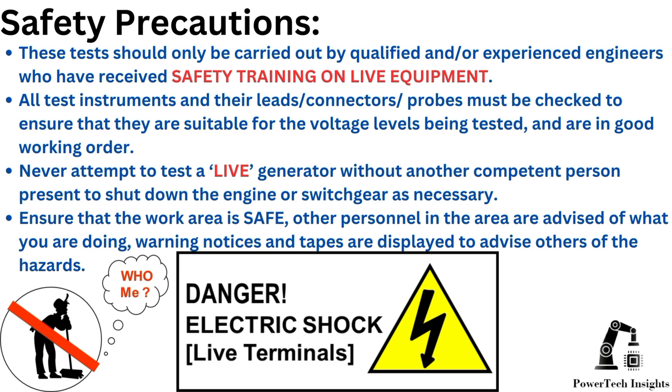All test instruments and their leads, connectors, and probes must be checked to ensure they are suitable for the voltage levels being tested and are in good working order. Never attempt to test a live generator without another competent person present to shut down the engine or switchgear as necessary. Ensure the work area is safe, other personnel in the area are advised of what you are doing, and warning notices and tapes are displayed to advise others of the hazards.